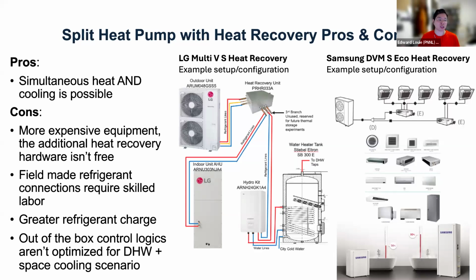There is definitely a higher cost in equipment associated with this heat recovery capability. So we're also hoping that in the future the packaging of this type of equipment would be made such that the additional cost is reduced, because right now this type of system is really designed for light commercial, and these manufacturers have just shrunken light commercial equipment down to residential sizes without really too much cost optimization effort. But in the future, we think that cost optimization effort can be an additional layer to make this equipment more accessible. Again, this type of equipment has field-based refrigerant connections. So again, skilled labor is required to install it in a leak-free manner.